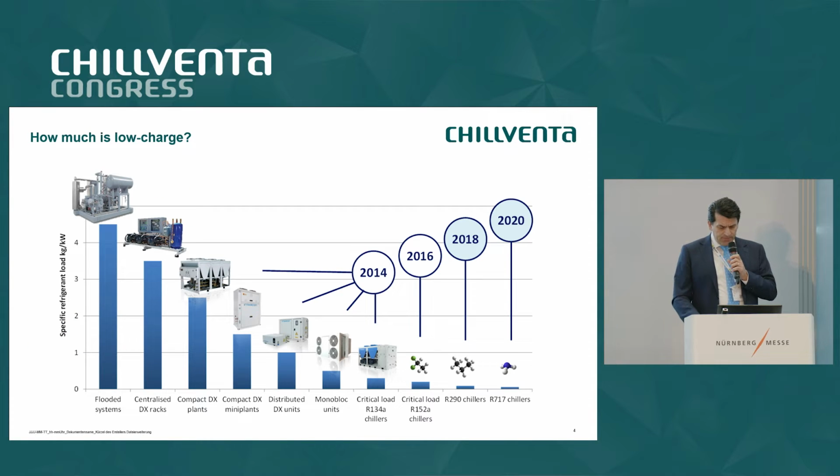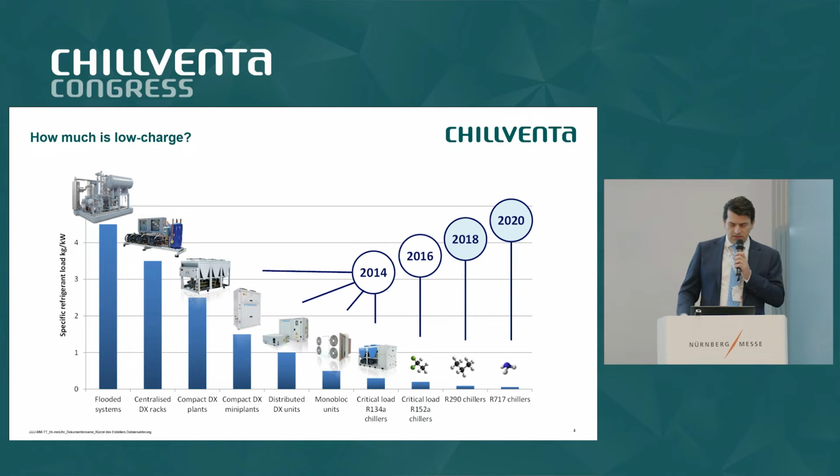At Intercon, for the past 15 years, we are a young company. This year is our 15th anniversary. We've been very much focused on reducing the charge of the refrigeration system throughout our small history. And if we look at the very early or traditional historical ammonia systems, pumped ammonia systems, overfeed ammonia systems, they used over 4 kilograms of ammonia per cooling kilowatt.